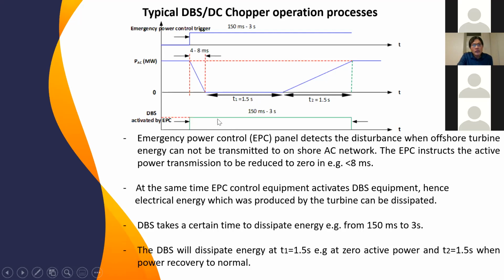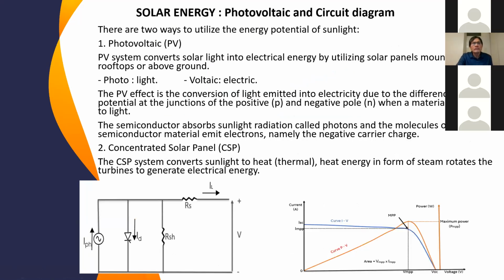the energy is still 0, absorbed by the DBS, and then suppose it is recovered, within 1.5 seconds of the fault there is still excess energy where the DBS is still working. So between instruction and activation to dissipate, all energy will be absorbed by the DBS or DC chopper. So now we finish the turbine, and we move to solar panel.